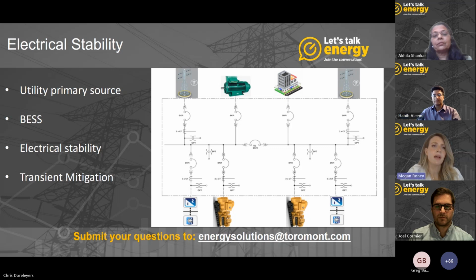Okay, great. Thanks, Habib. And lastly, is a microgrid controller needed when a battery energy storage system is used with other power supplies? In most microgrid applications or hybrid systems, a microgrid controller is used to manage the different power sources. Also, a microgrid controller could be used to program different modes of application. It could be one point of connection for a customer SCADA or remote monitoring system, and it could provide alarms and data to the customer.